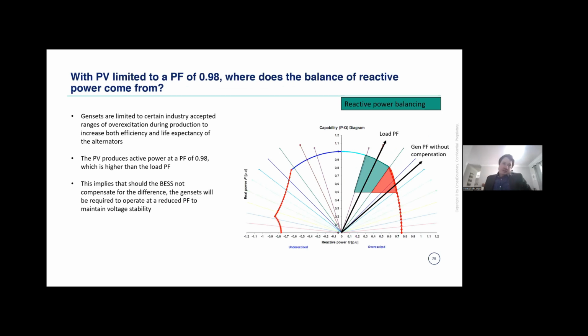But this comes with other challenges. So with solar PV limited to a power factor of 0.98, there's obviously a balance of reactive power that needs to be supplied, considering we're sitting with a load that is operating at a power factor of about between 0.79 and 0.9. And if we consider no BESS application at the moment, then essentially the generators would need to be providing this additional reactive power. And what this would essentially imply was that our gensets would be moving away from the efficient operating point down to being overexcited, which could lead to less efficient operation or possible damages to your alternator in the long run.